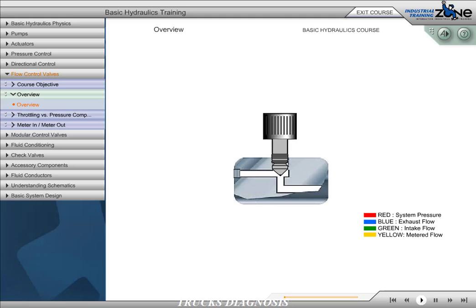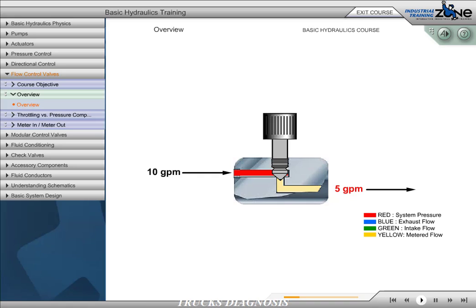The function of the flow control valve is to reduce the rate of flow in each leg of the circuit. Flow reduction will result in speed reduction at the actuator. A flow control valve builds added resistance to the circuit, increasing pressure, resulting in a partial bypassing of fluid over the relief valve, or a de-stroking of a compensated pump. This reduces flow downstream of the flow control valve.